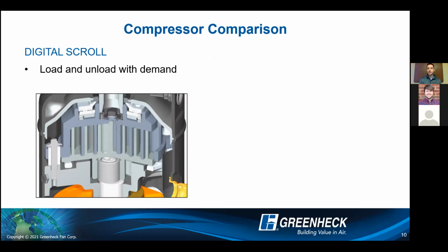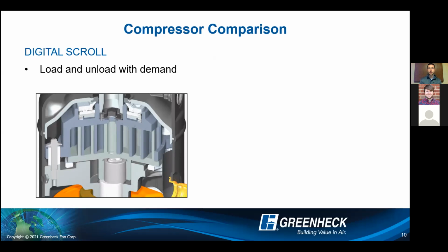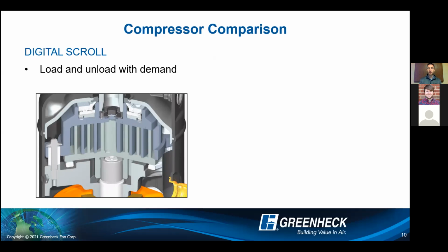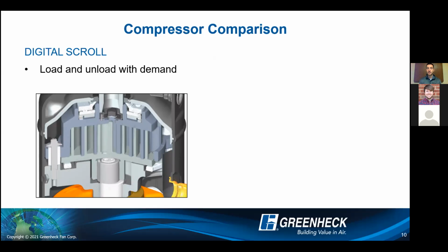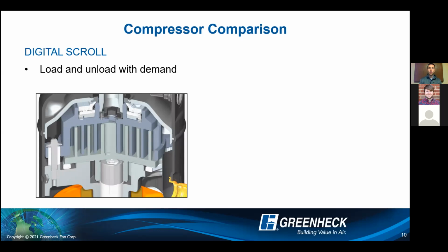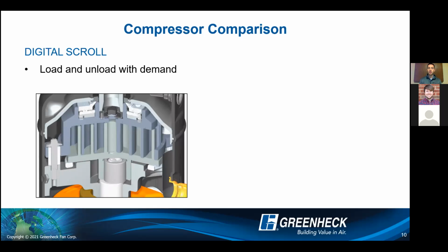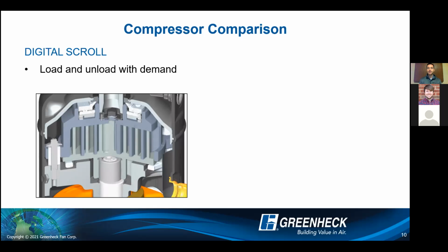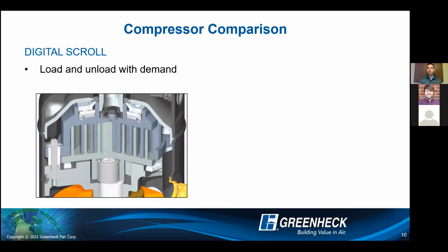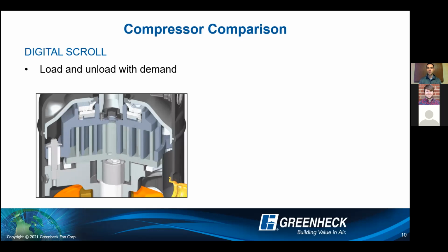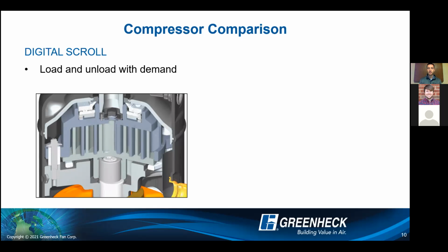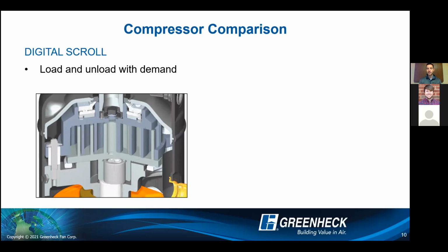And based on the capacity required, let's just say 50%, it's going to load for 7.5 seconds and unload for 7.5 seconds based on that 50% capacity requirement. But when it loads and unloads, even when it's unloaded and not technically compressing, it's still rotating at full speed and the motor's operating at full speed as well. So it's very inefficient from a part load condition. So when you get to those part load days, it's going to be unloaded a lot more than loaded, which means you're not compressing, but you're still wasting a lot of energy.